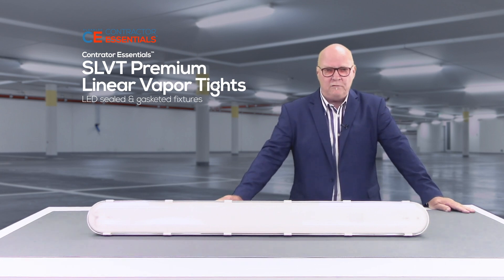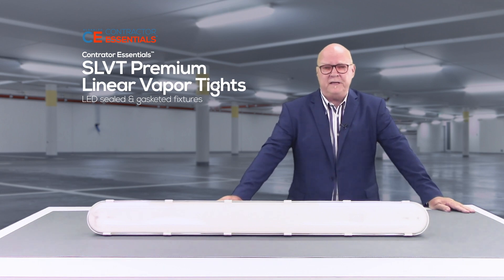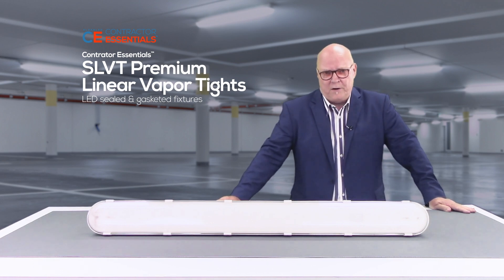These listings are made possible by the tongue-and-groove lens-to-body design with a poured-in-place gasket that's compressed by 12 latches on the four-foot fixture and six latches on the two-foot fixture. These latches are available in both polycarbonate and stainless steel, and both have options for the provision of tamper-proof hardware.